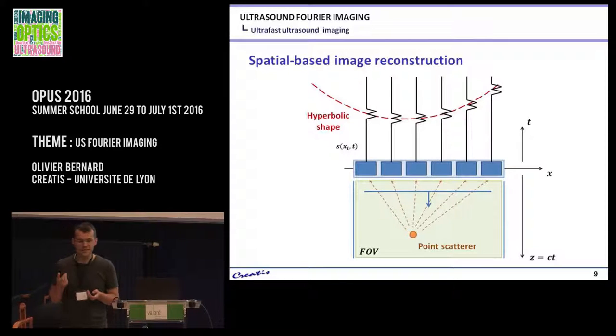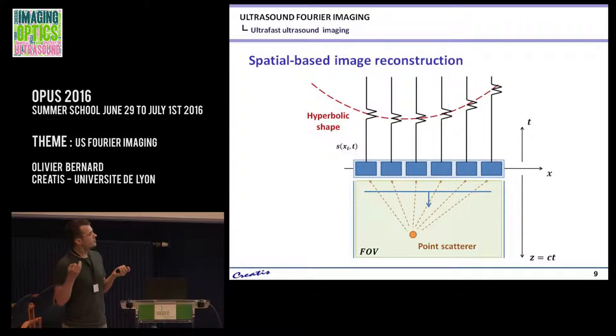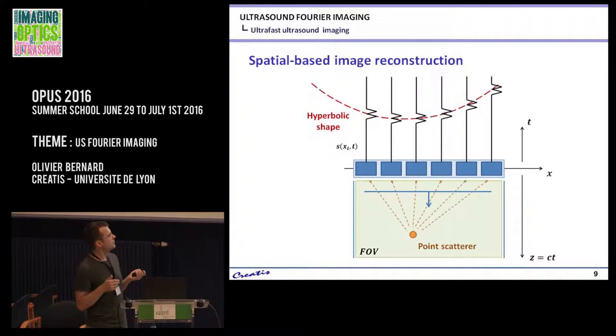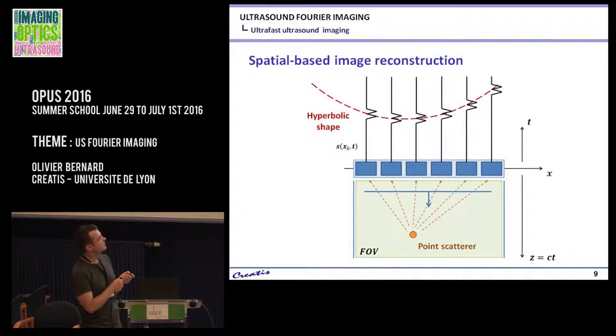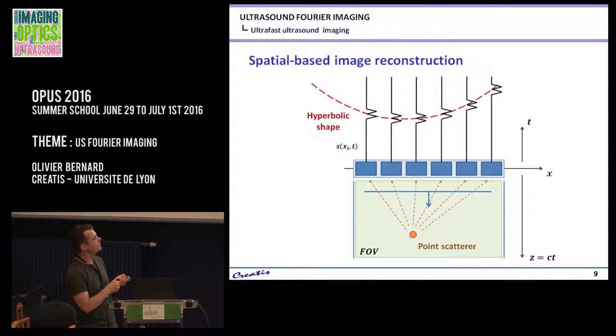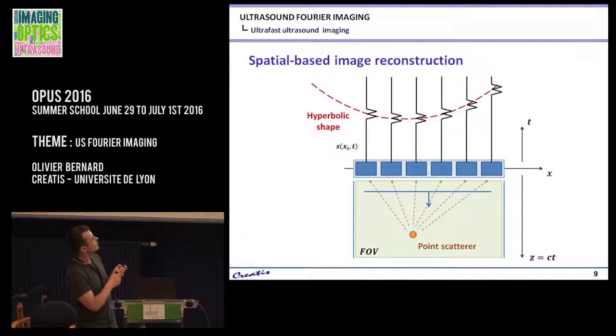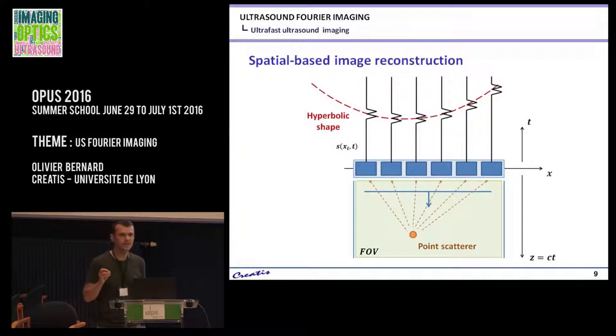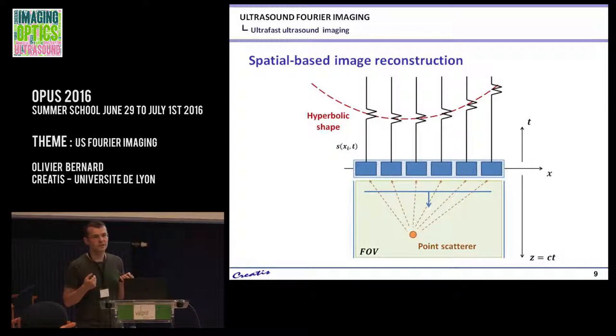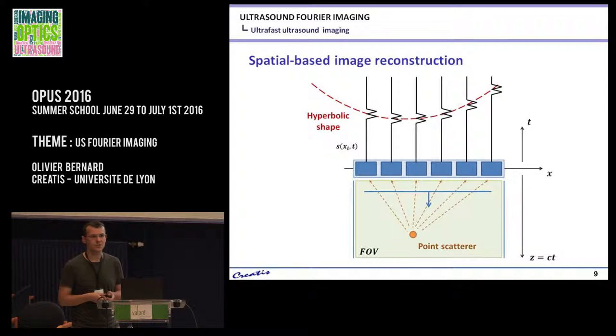Going back to the spatial-based approach: imagine you have only one point target and you emit a plane wave. By the time this target is insonified by the wave, it provides an answer back to the different elements. This information will not arrive at the same time, depending on the relative position of the point scatterer with respect to the different elements. Thanks to basic mathematical law, there is a hyperbolic shape corresponding to the same information from the same point scatterer. So for each point in the medium you want to reconstruct, you do the hyperbolic integration of the information and iterate for each point. This is the spatial-based approach.